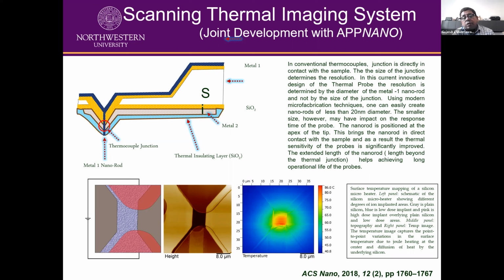Suppose your sample temperature is pretty high. If you use a normal thermocouple probe directly hitting the surface, the probe will bend because of the heat. But here, the thermocouple is not in contact with the sample. A metal wire comes out through the thermocouple, and that wire makes contact with the sample surface. That allows us to image thermal structures and nanostructures down to 20 nanometers, which is not possible with any other technique.